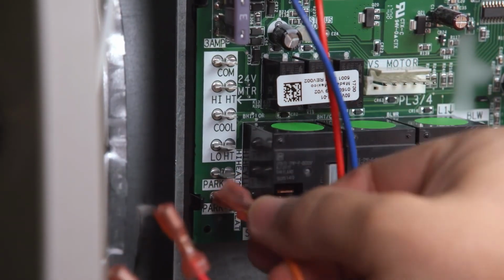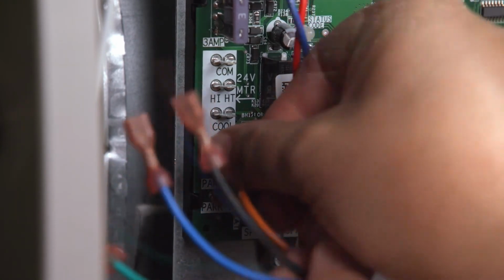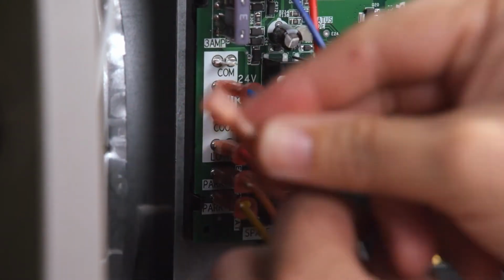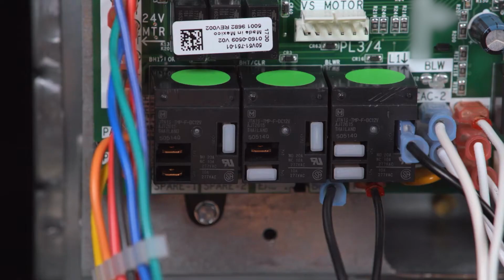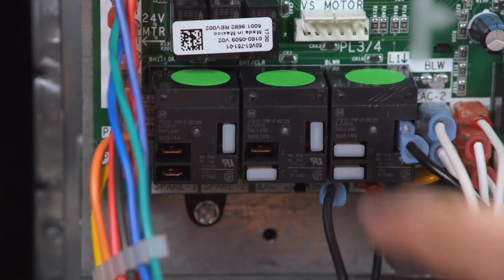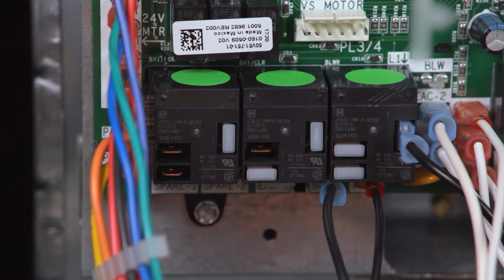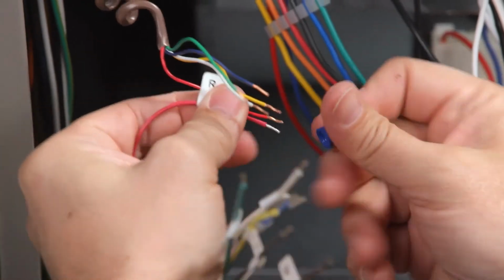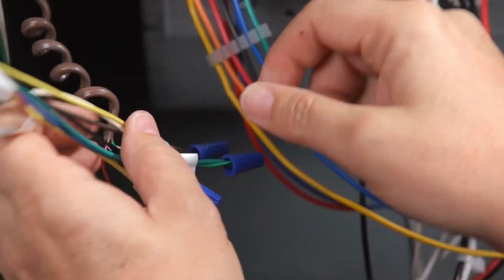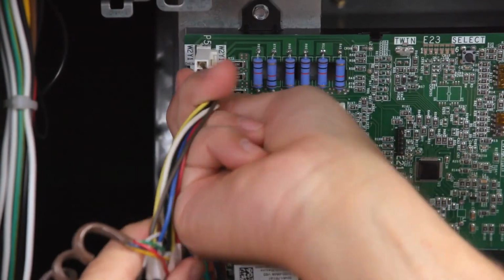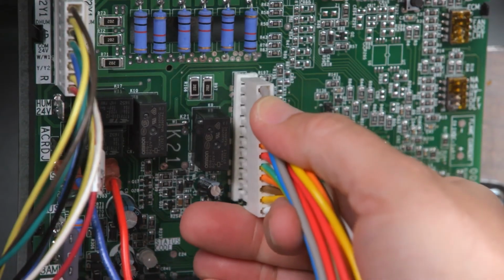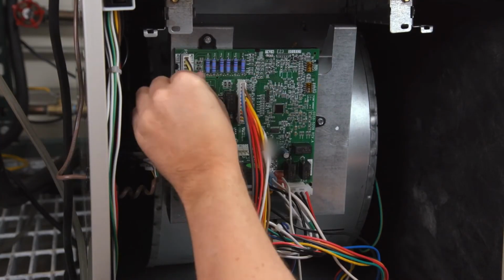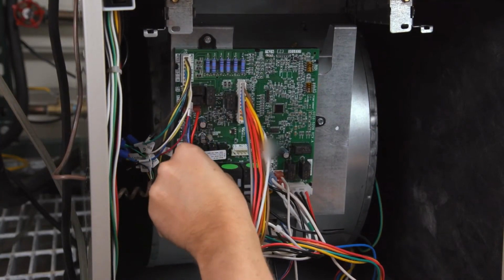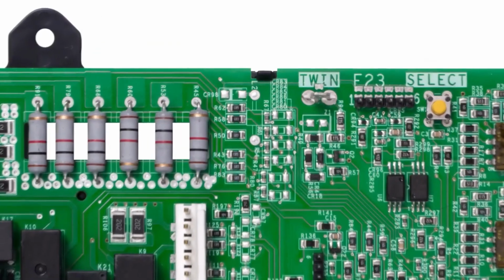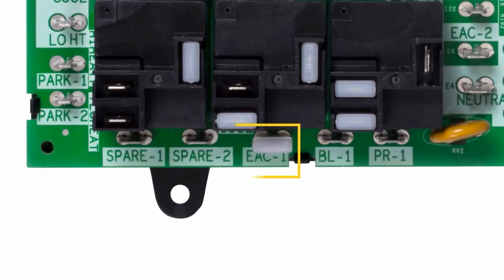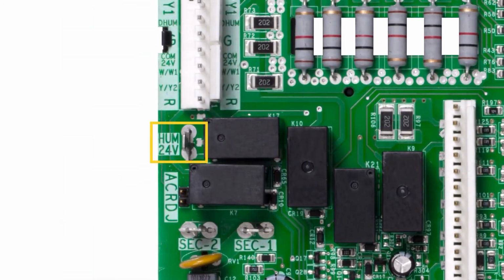Connect low-voltage ECMx blower motor wires for park, low heat, cool, high heat, and common to the 3/16-inch spades. If you are installing in a PSC blower application, the 1/4-inch motor connectors are located on the relays. Connect thermostat wiring. Use adapter A and wire nut thermostat wires to label adapter wires. Then plug adapter A into the inline thermostat connector. Plug in the Carrier inline plug. Ensure all wires are secured to the control board and unused blower speed wires are attached to the park terminals. This control also features a twinning terminal, a 120-volt electronic air cleaner accessory terminal, and a 24-volt humidifier terminal.